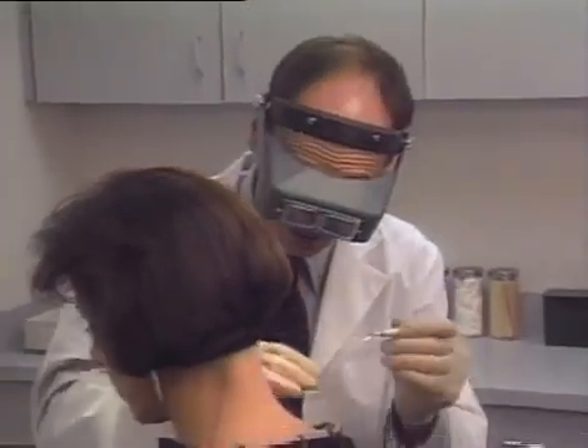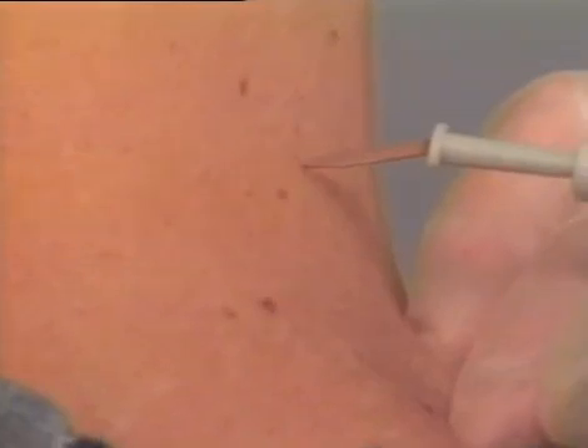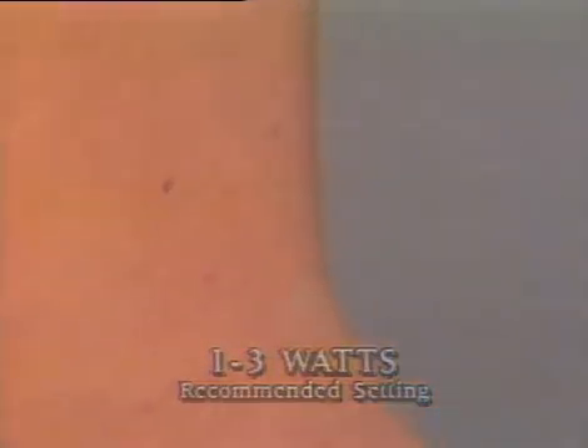Numerous small skin tags may be treated very quickly using the Hyfrecator Plus at low power settings. You apply the current to the tag for one half second or less — the tag will blanch but does not fall off. You can tell the patient to expect the lesion to dry up and fall off over the next few days. For lesions up to one to two millimeters in size, a current activation of one to three watts is applied for less than one second, so no anesthesia is required. However, if something appears unusual about the tag or if it is particularly large, you should remove the lesion with a shave excision to provide a specimen for biopsy.